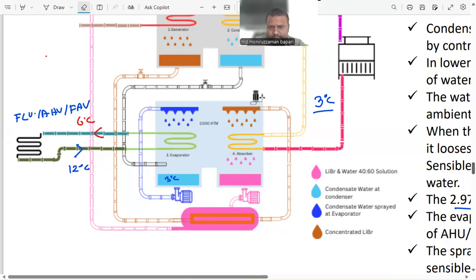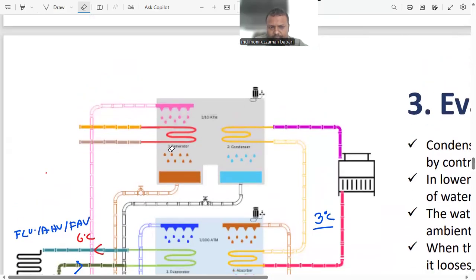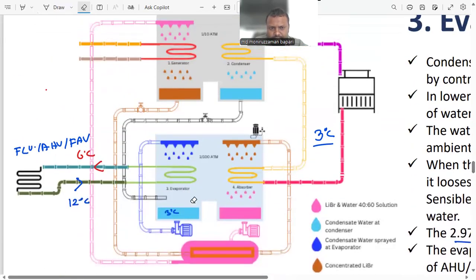Okay, these are the total 4 steps. Step 1, lithium bromide generated. Step 2, vapor is condensed. Step 3, we have evaporation, like this water is going to evaporate. And finally, absorber, the water vapor is going to be absorbed. This process goes on, and as an outcome, we get cold water at the output here. And we are going to deliver it to the fan coil unit and air handling unit. Anywhere there is a cooling coil, we are going to deliver this, and we are going to get hot water from the cooling coils.